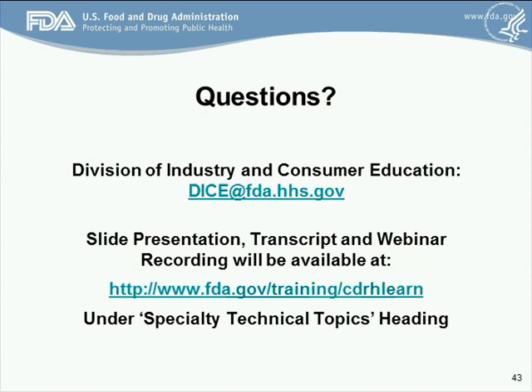The final question comes from Dylan Zygmott of Millstone Medical. His question: regarding pyrogen testing, what does FDA consider a batch — is it one single lot of product, or can it be a whole batch sterilized at the same time? The response: refer to AAMI ST72 for that, as it provides information in the body of the standard as well as information in the annexes about small batch release. If it's not clear, get in touch with DICE to find one of our experts to talk to about that. It's always good to have that information before rather than after making your submission.